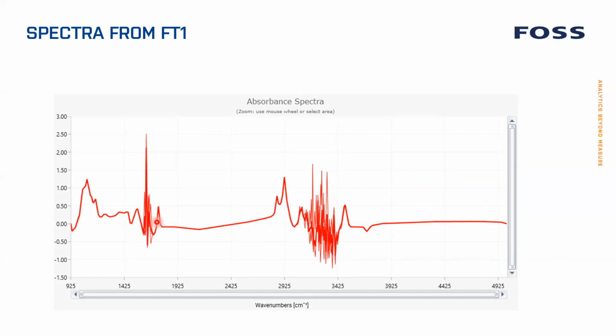For the Milkoscans, we use water as a reference. So when you scan a sample, the water peak is actually removed. That's why it's very noisy in these areas, but the rest of the area you can use for all the other determinations we do. And that will of course be similar for FT-NIR instruments, where the water peak is much smaller, and they normally use air as a reference.